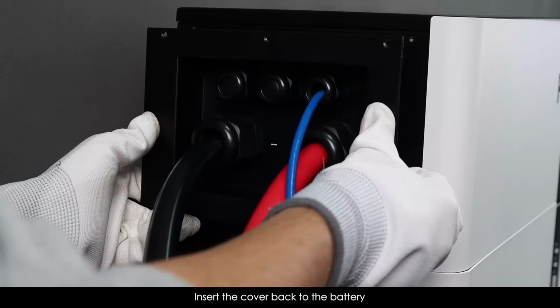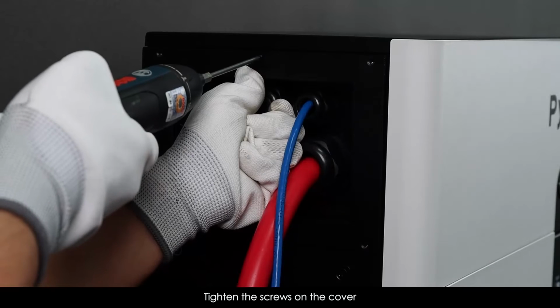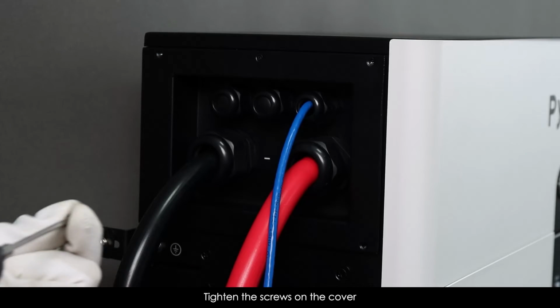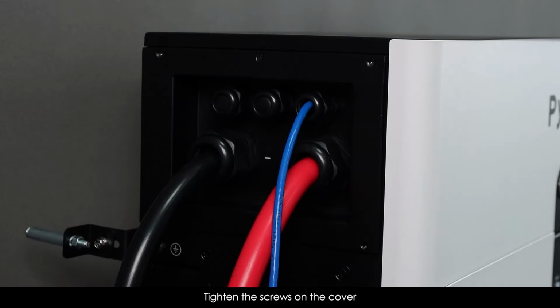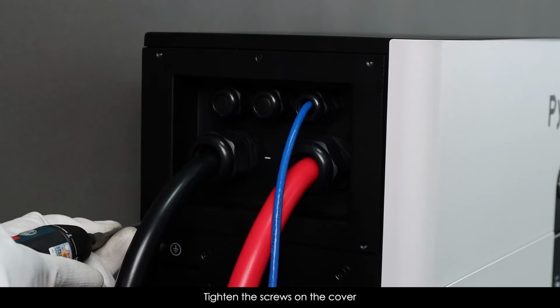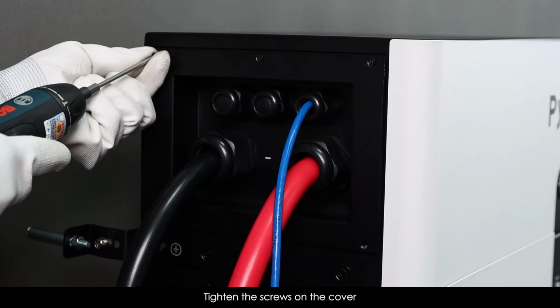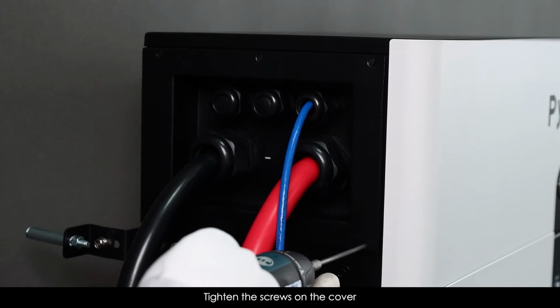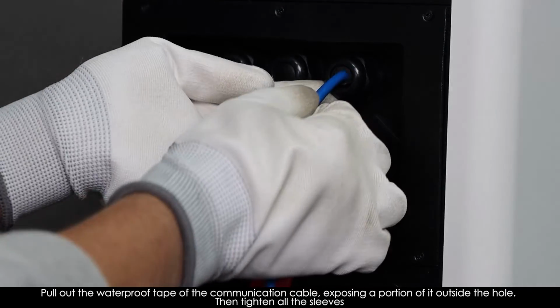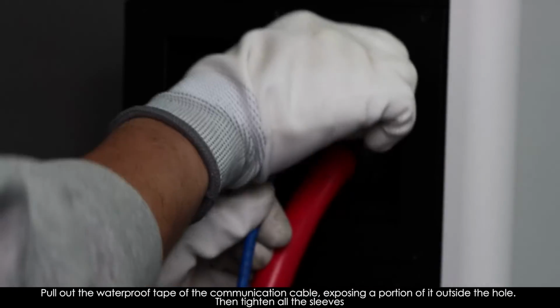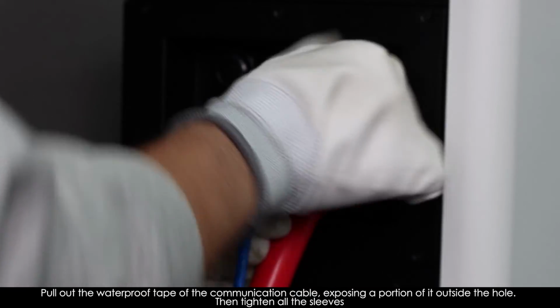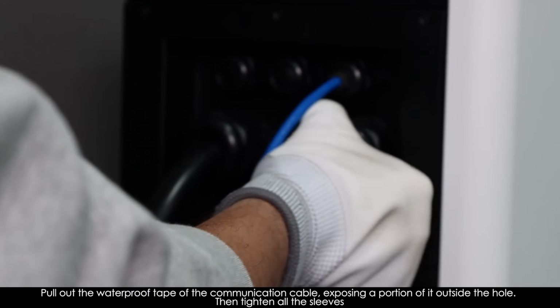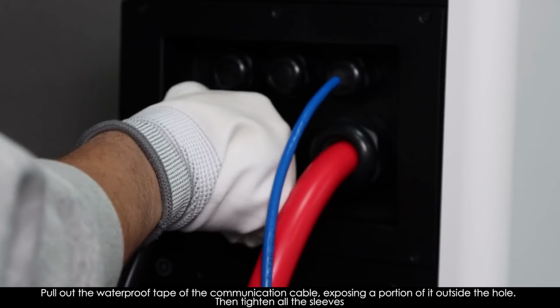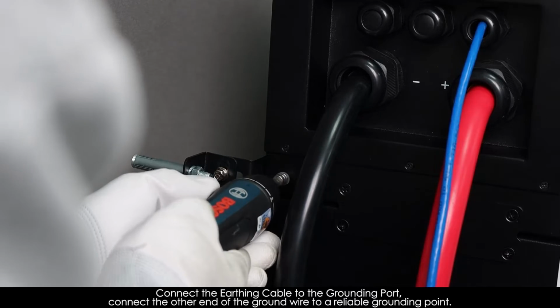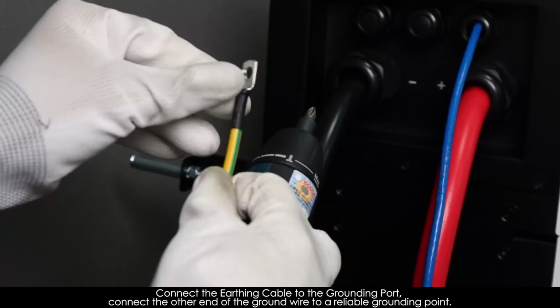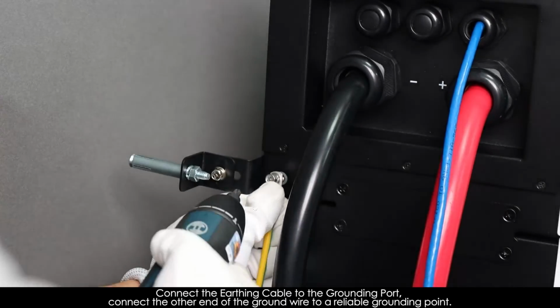Insert the cover back to the battery. Tighten the screws on the cover. Pull out the waterproof tape of the communication cable, exposing a portion of it outside the hole, then tighten all the sleeves. Connect the earthing cable to the grounding port. Connect the other end of the ground wire to a reliable grounding point.